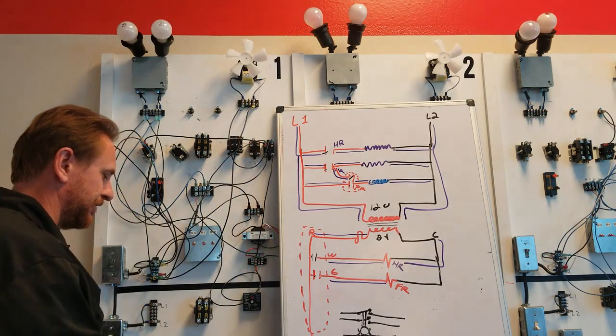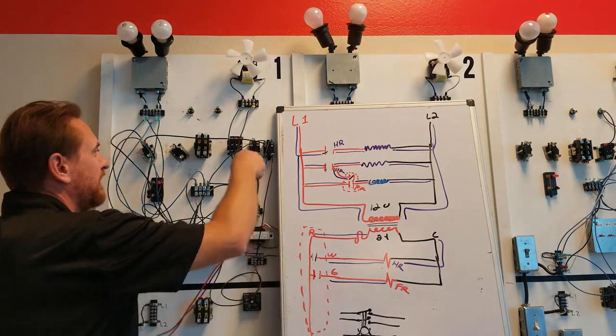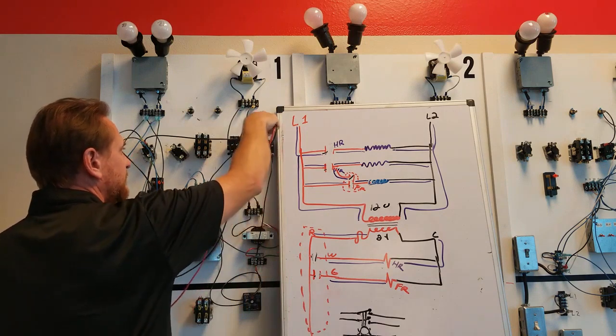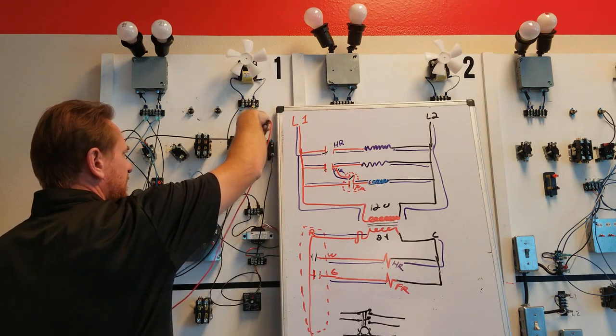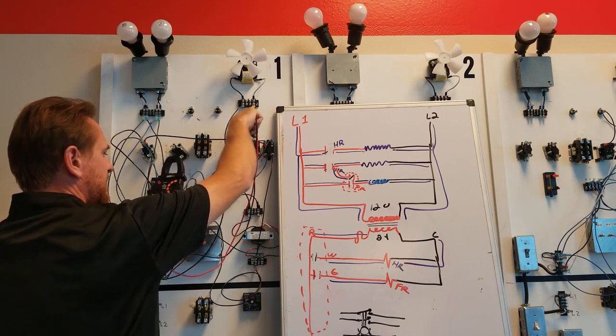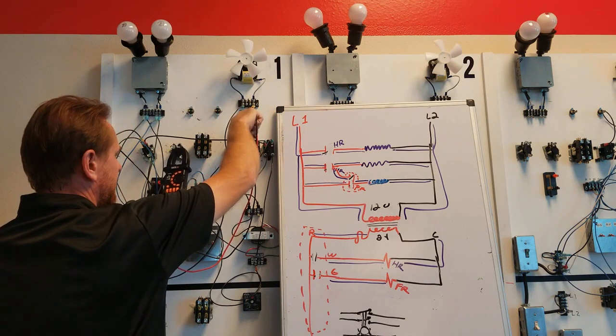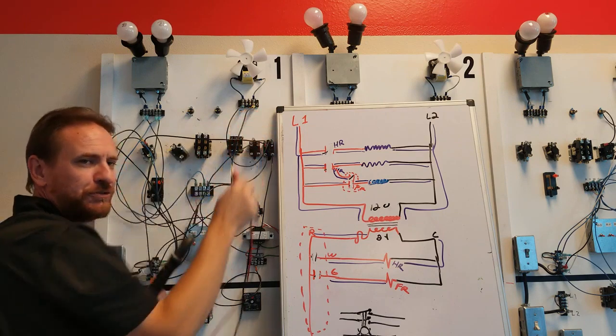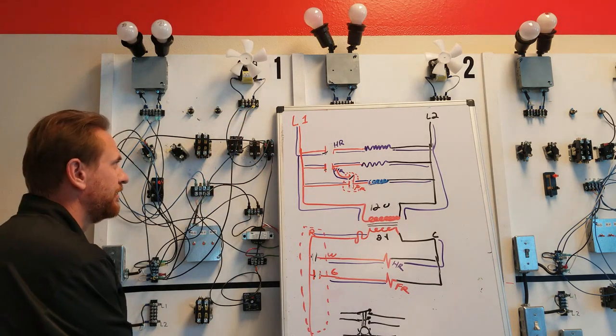Let's see what those do. So we take our meter, we put it over here to the set that's not numbered at all. One side and the other. I check with the meter, firmly press against it, and I'm getting 18 ohms resistance. So that is a load.